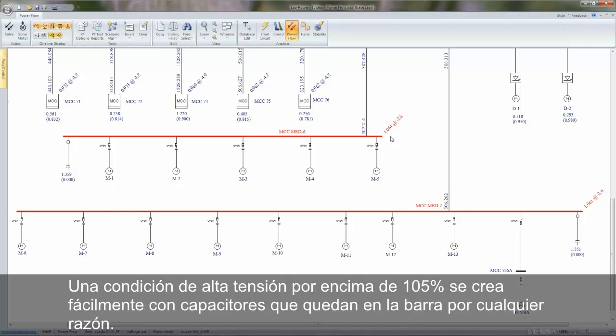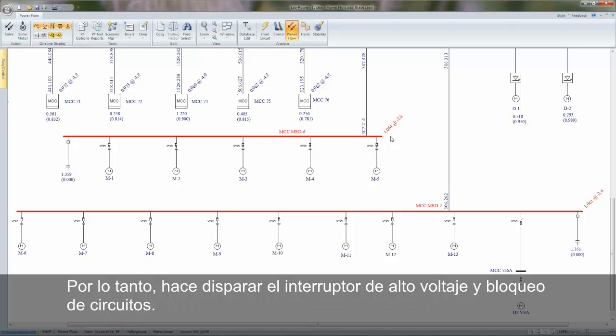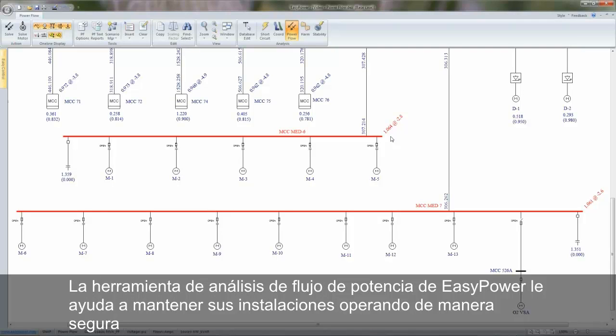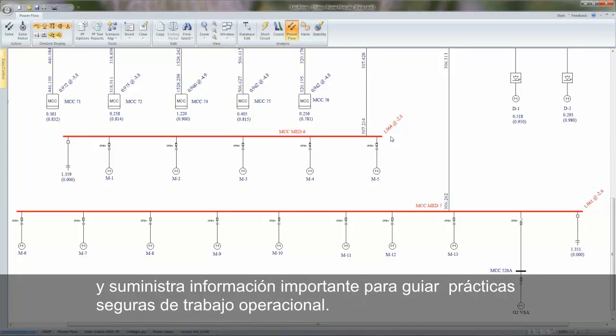A high voltage condition above 105% is easily created with capacitors left on the bus alone for any reason. So apply a high voltage trip and lock out the banks. The EasyPower power flow analysis tool helps you keep your facility operating safely and supplies important information to guide operational safe work practices.